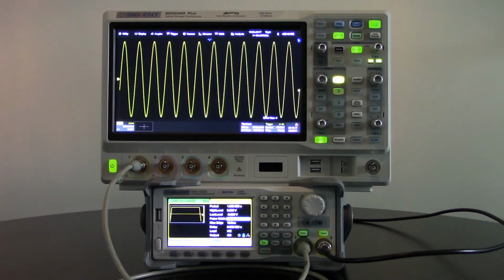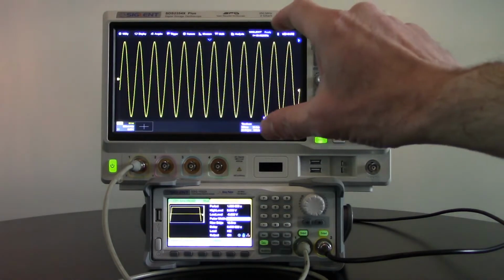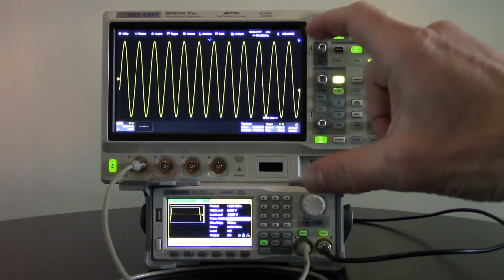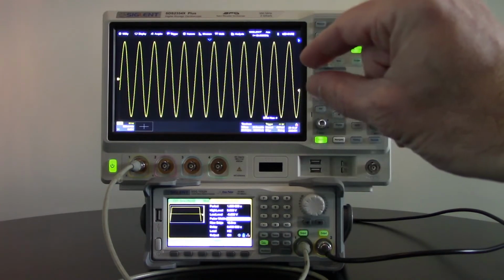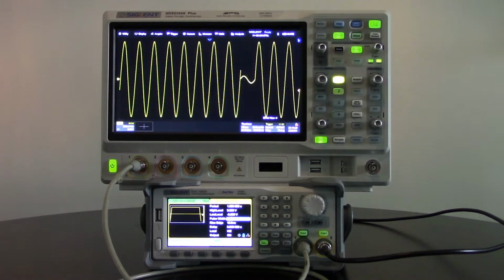I had a customer call and they were doing dirty power testing. In dirty power testing, the sine wave, the voltage coming in, instead of being the max voltage, you actually get dropouts or smaller events that occur. A brownout is another way of putting that. So the power coming into the instrument or the device that you're testing is not consistent over time.